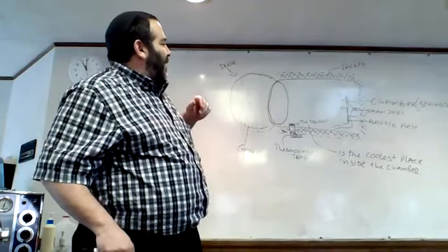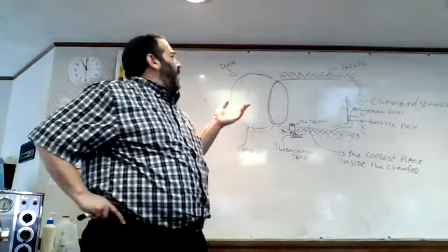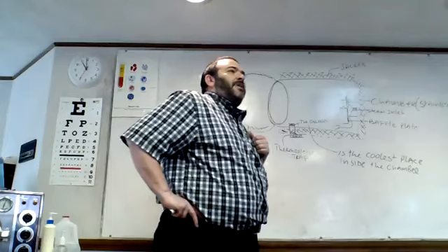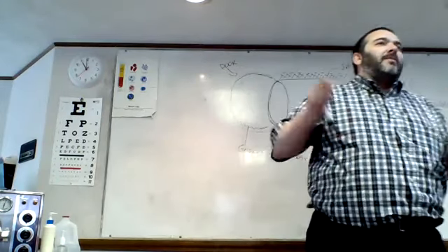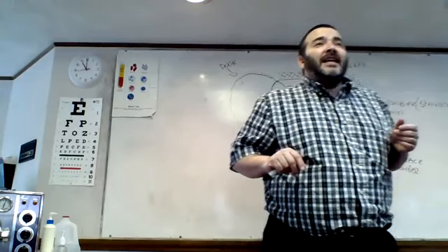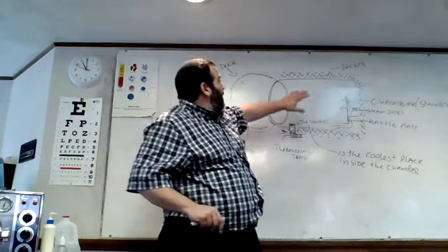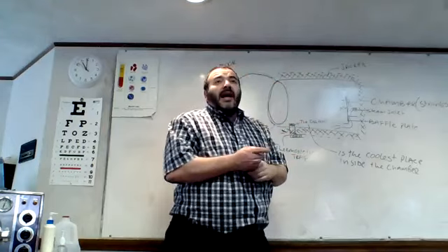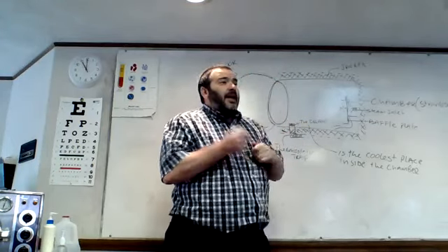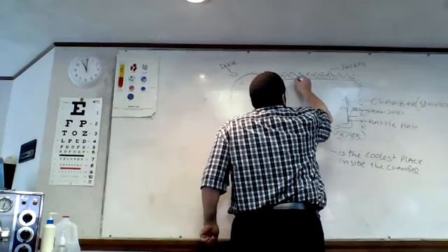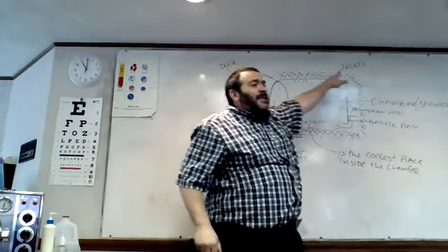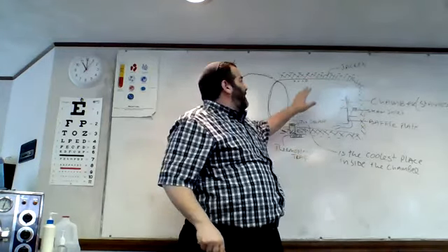Now, the question then becomes, why do I need a jacket around the chamber? Well, because unlike our pressure cooker, where temperature fluctuations on the outside don't really matter much, for sterilization, if the air is really cool inside the room where the sterilizer is, cold air is going to touch my chamber, and what's going to happen to the steam around the edges? It's going to turn into liquid, into droplets. The jacket keeps the outside of the chamber just as hot as the inside of the chamber.